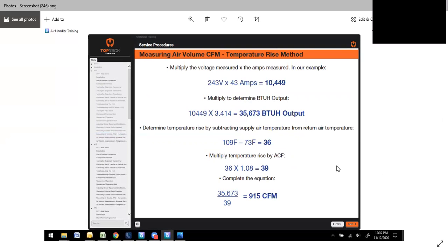So we'll come over here. In this case, we multiply the voltage times the amps in our example. We're not crazy: 243 volts times 43 amps, multiplied to determine the BTU output. You'll have 10,449 times 3.414, which will give you 35,673 BTU output.